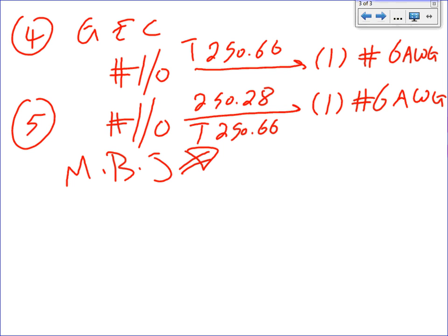Quick question. Yes, sir. You have your DeWalt, right? Page 550, 5-13, if I'm interpreting it right. Yep. So the electrode conductor never exceeds 3/0. Yes. But if the bonding jumper is over 1100, then you do 12.5%. Yes. All right.